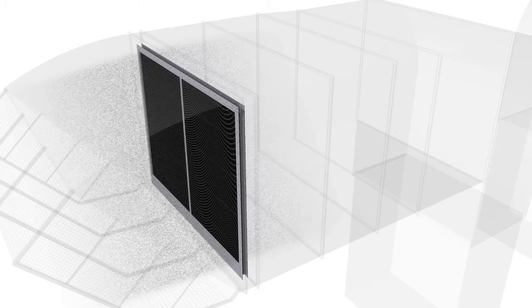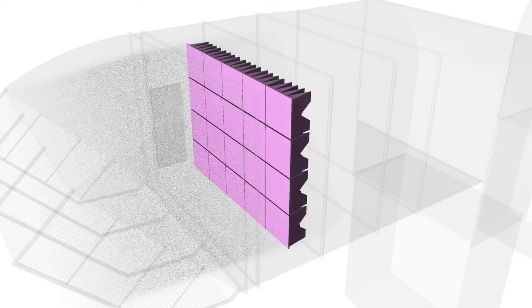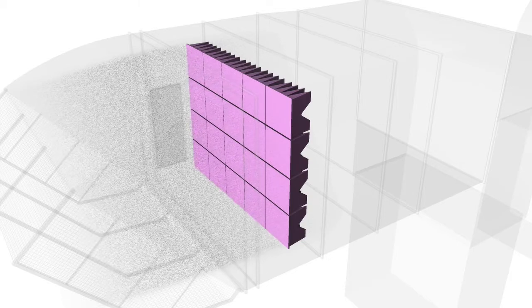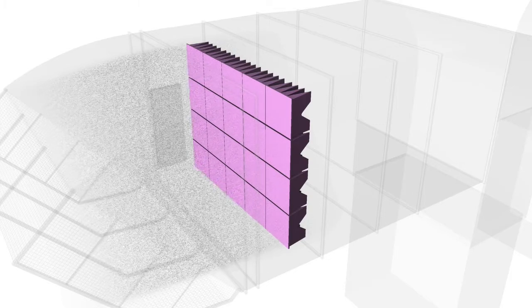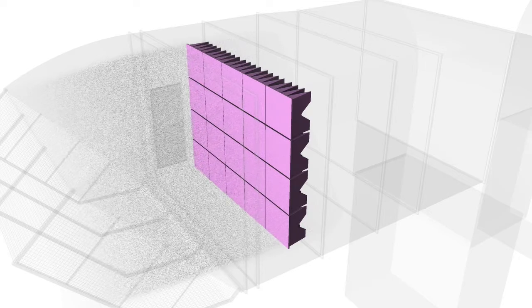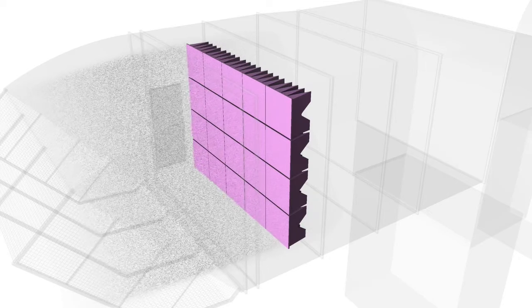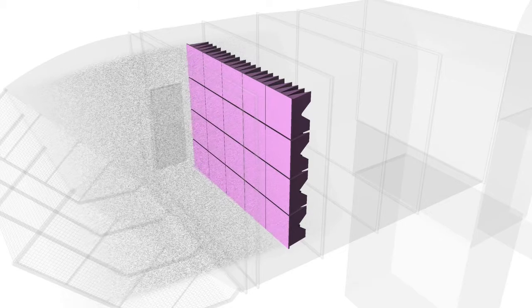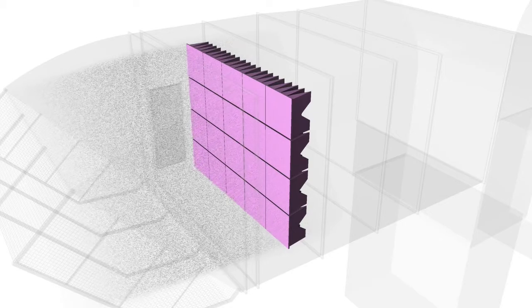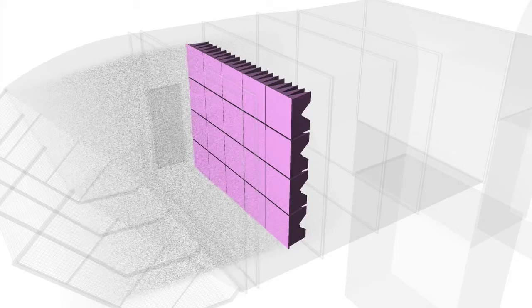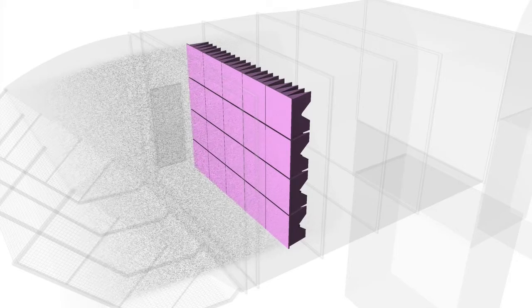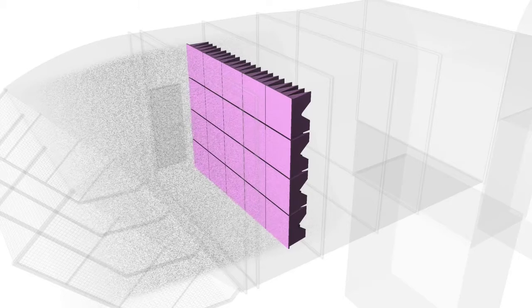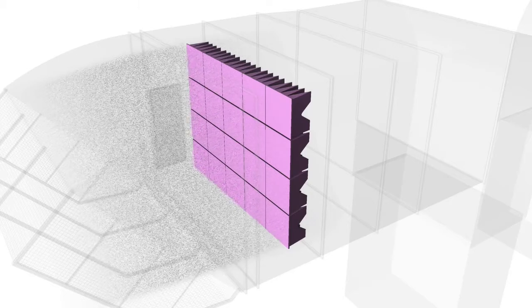Stage 2 is the coalescing pre-filter. This cleanable filter has two functions. The first is to coalesce fine salt aerosols, those too small to be captured and removed by the first stage separator. In this situation, captured salt aerosol either drains through the media to the drainage system in the filter house floor or is re-entrained into the airstream as larger saltwater droplets which are removed in the later stages of the filtration system.